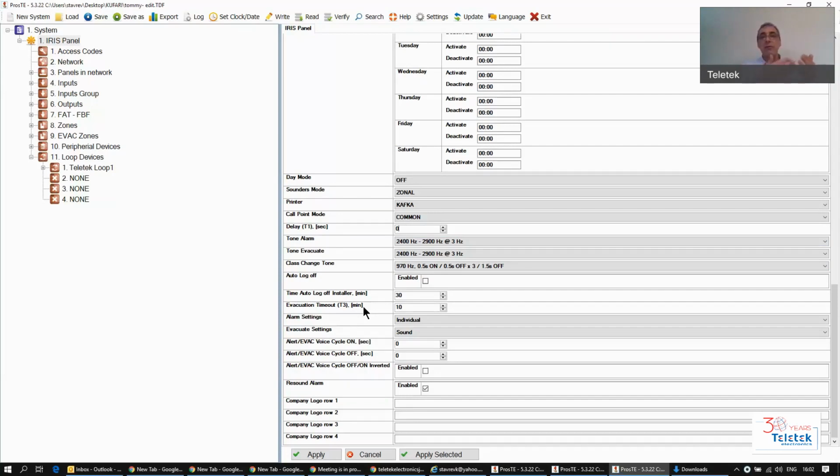This is the problematic floor. You want to evacuate the people first, because if you evacuate all the floors at the same time, you might get staircase congestion, and the people from the problematic floor might not be able to go out and evacuate the zone.